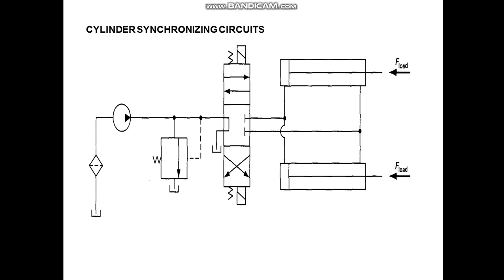Synchronization means we have to operate two or multiple cylinders in a synchronous manner. Synchronization is achieved by keeping the velocities of all connected cylinders the same. Extension of all cylinders must start at the same point, all cylinders will extend at the same time, and all cylinders will retract at the same time. That is what is called a synchronization circuit.